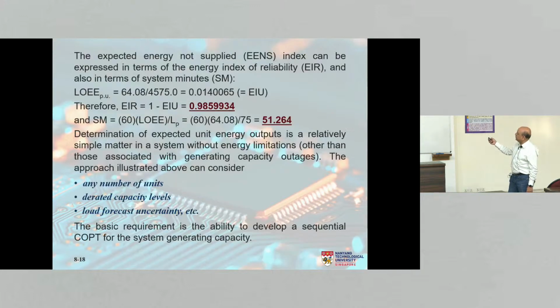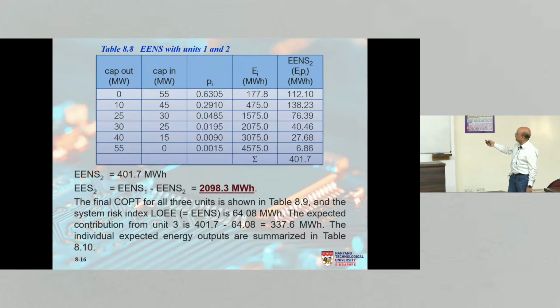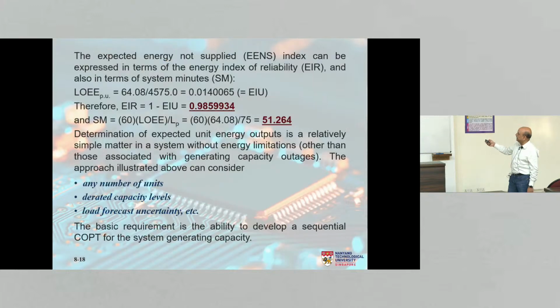So the expected energy not supplied index, 64.08, if you divide it by the total energy required, which is 4575, we saw that earlier, right? The total energy required is this one, 4575. So if you divide it by that, you will get the energy index of unreliability. And of course, its complement is the energy index of reliability. And then system minutes, you can calculate, you find 51.2.